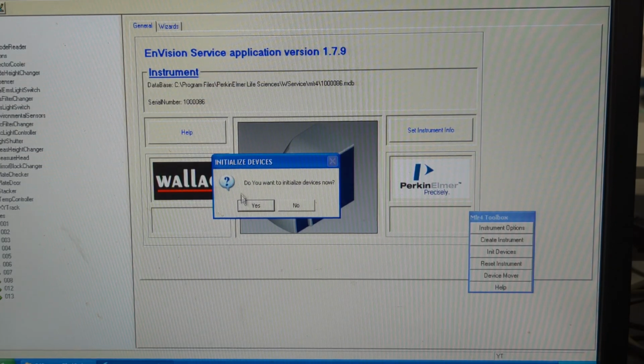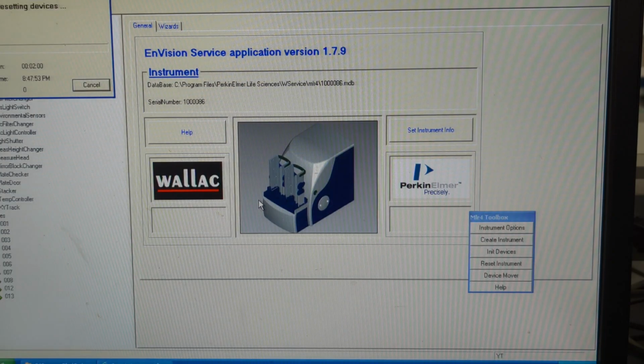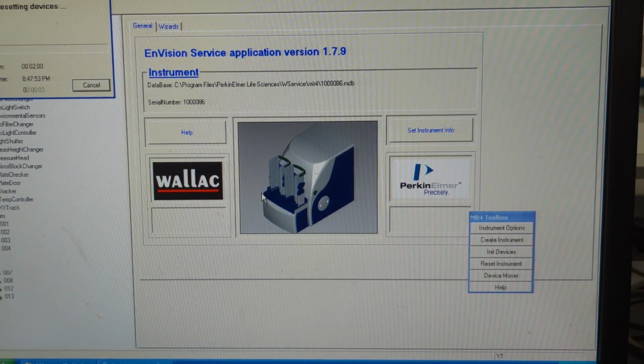You might have to try it a couple times depending on how old your instrument is, or that doesn't happen with the other one, but it does happen with this one. And now it's asking us to initialize, so we're going to click yes. And you can hear that the instrument is initializing. It's really just moving all of the internal motors through. It's homing them. It's just running everything through a quick startup test.